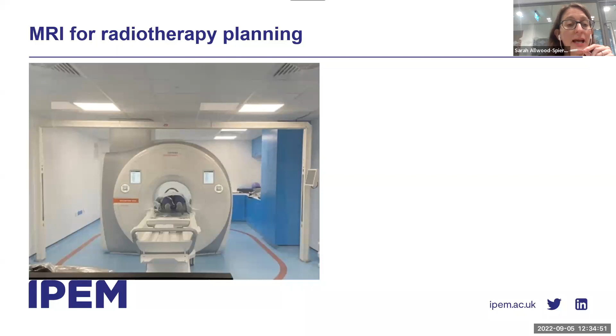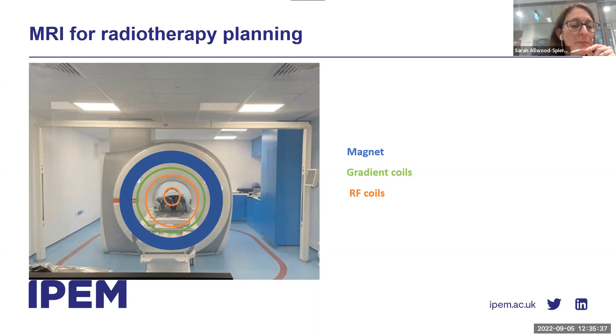Under the covers, a typical MRI scanner has a superconducting magnet, shown in blue here, which is cooled by liquid helium, and this creates a strong magnetic field in the center of the scanner. We then have our gradient coils indicated in green. We can run currents through these to change that main magnetic field slightly, and we need these to turn any signal from the patient into an image. The third component is our radio frequency or RF coil, shown in orange here, and this is needed to transmit a radio frequency pulse of energy to the patient to create a signal. We then need other RF coils that we place close to the patient to receive the signal.